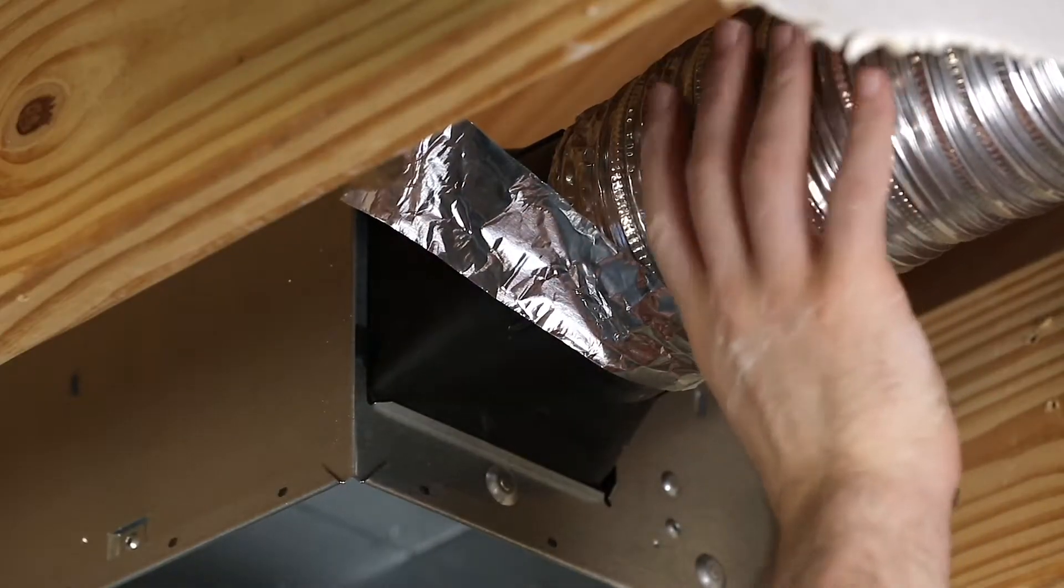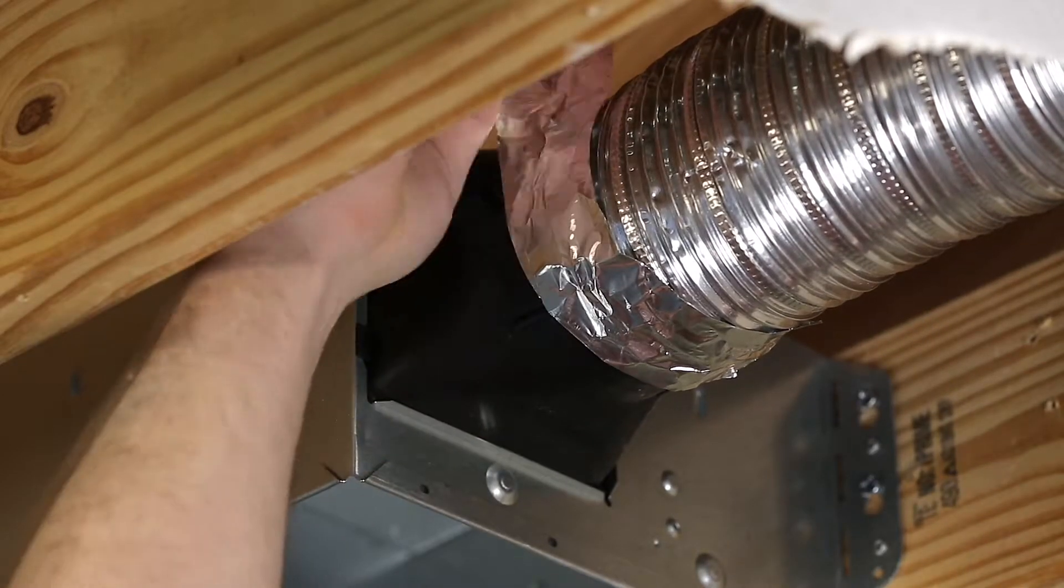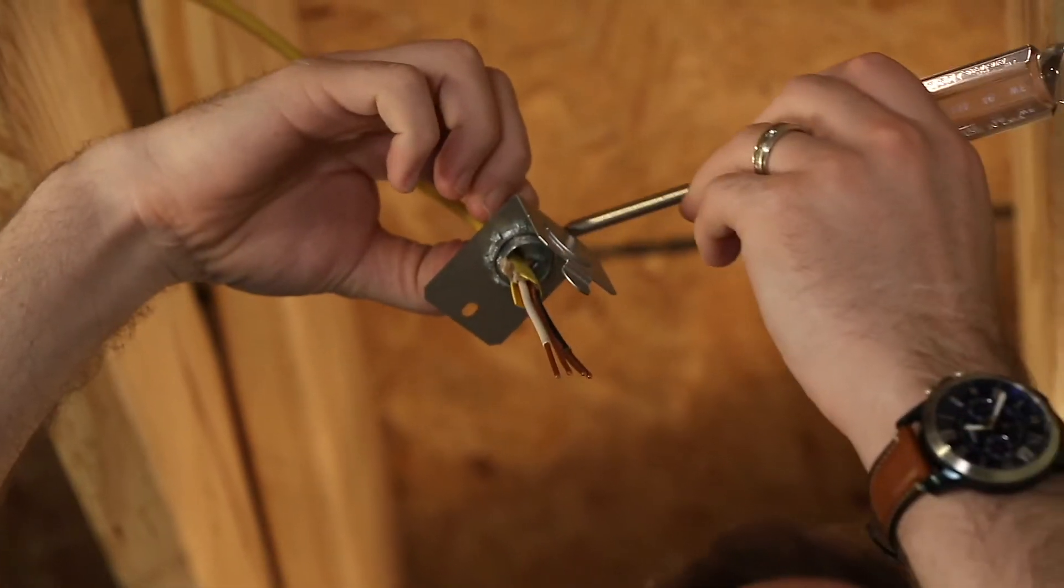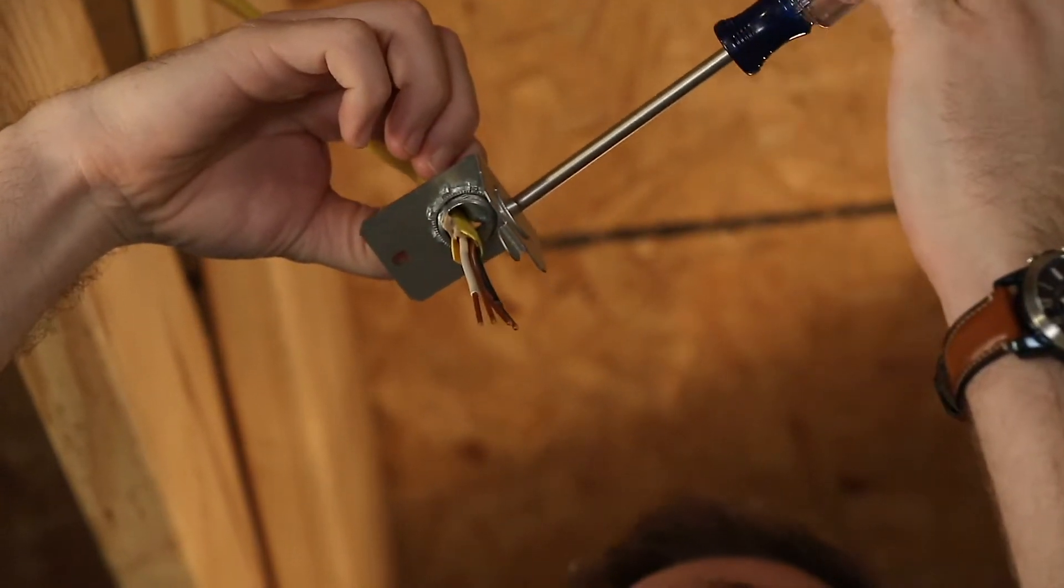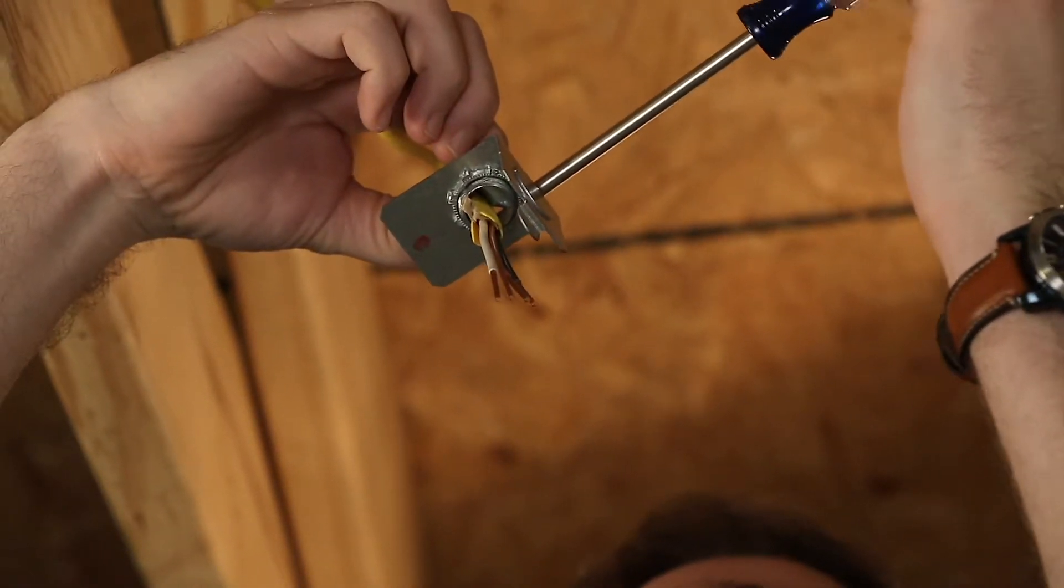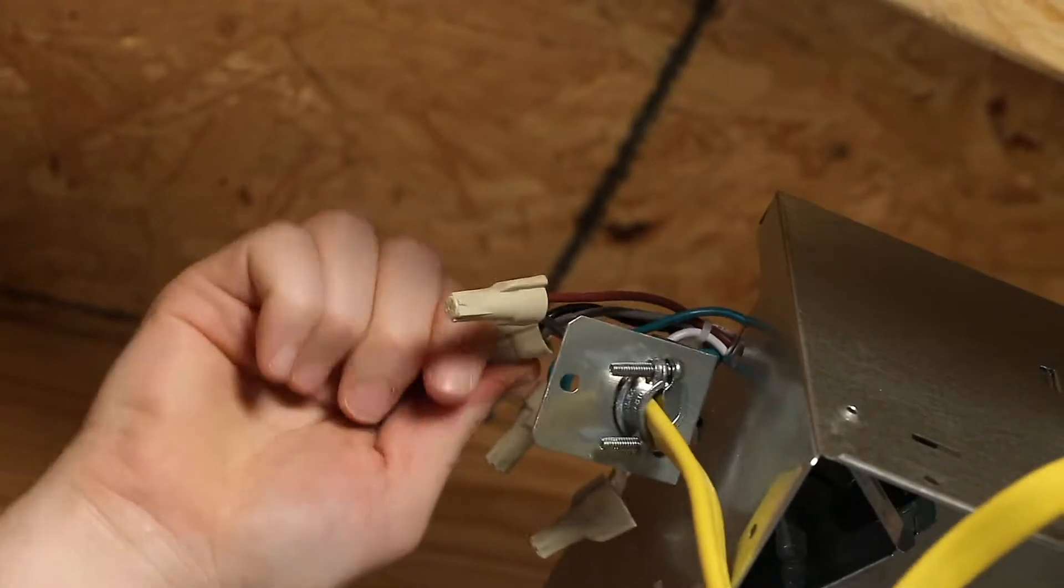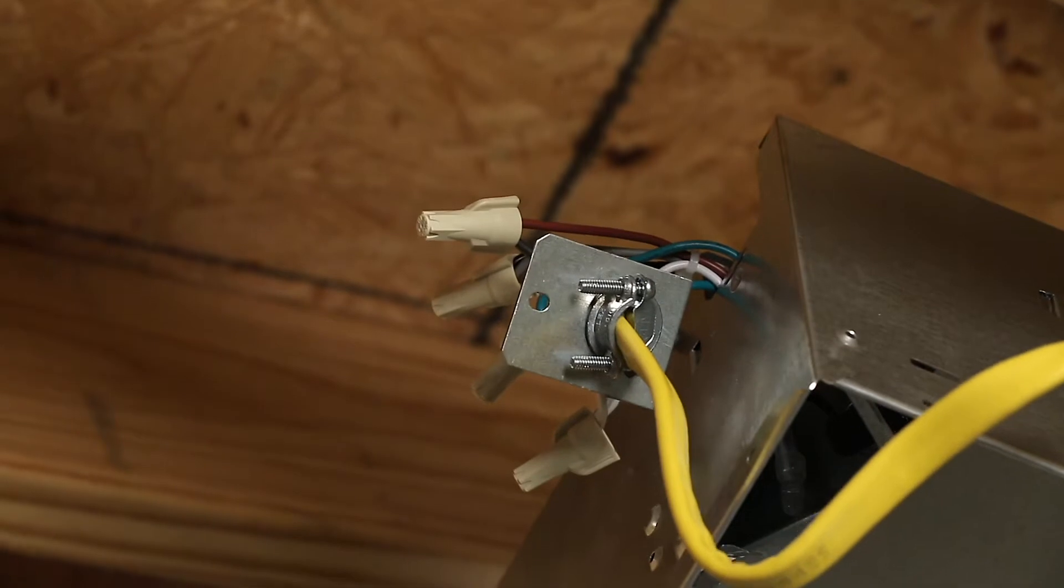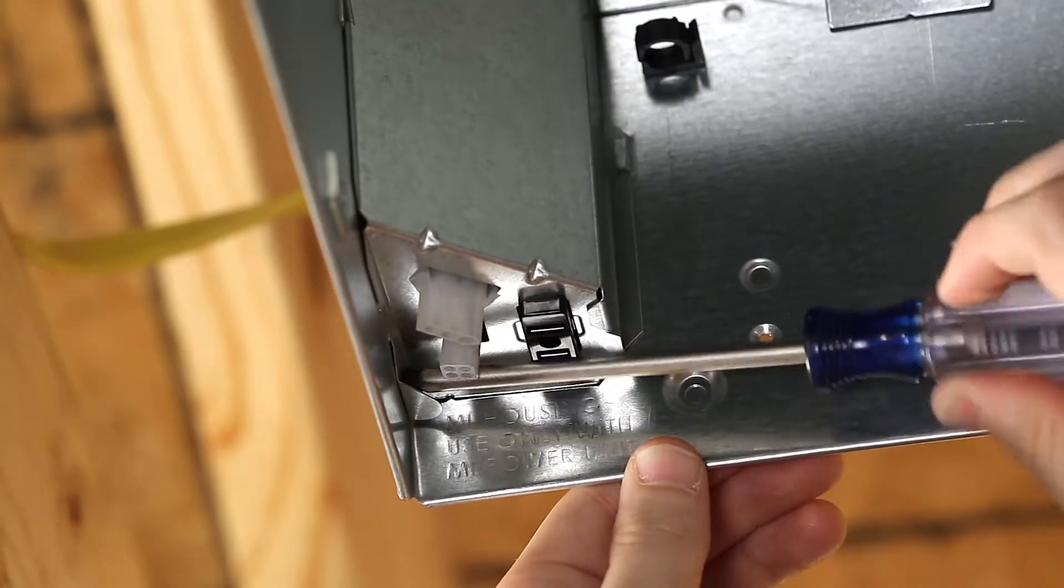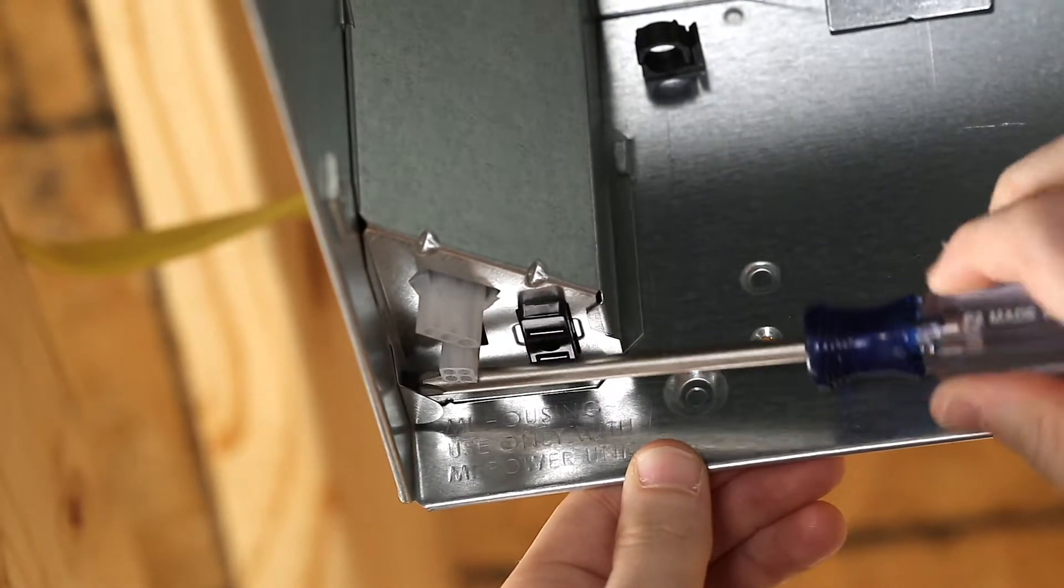Connect 4-inch round duct to the duct connector using duct tape. Next, connect the wiring. Connect the power cable to the housing with the appropriate UL-approved connectors. Follow instructions given for proper wiring. Reinstall the wiring panel and secure with screw provided.